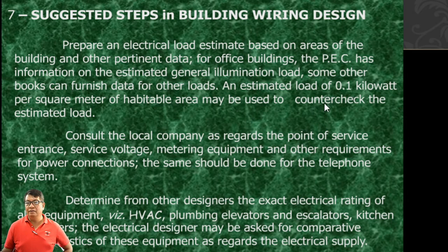Estimated load per square meter is 0.1 kilowatt or 100 watts per square meter of habitable area, and may be used to counter check the estimated load.